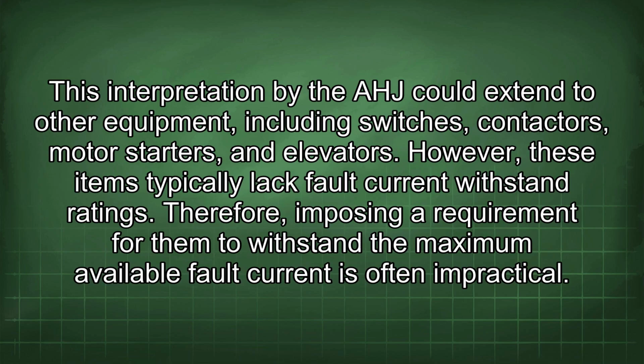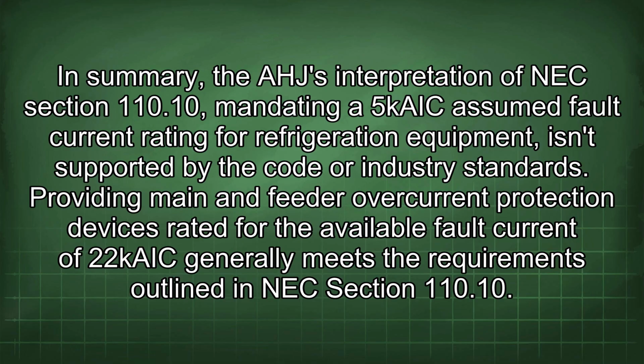current. This interpretation by the AHJ could extend to other equipment, including switches, contactors, motor starters, and elevators. However, these items typically lack fault current withstand ratings. Therefore, imposing a requirement for them to withstand the maximum available fault current is often impractical. In summary, the AHJ interpretation of NEC Section 110.10, mandating a 5kAIC assumed fault current rating for refrigeration equipment, isn't supported by the code or industry standards.